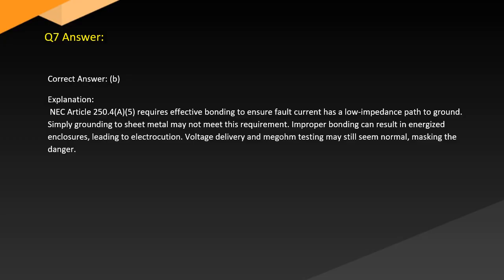Answer. Correct answer: B. Explanation: NEC Article 250.4(A)(5) requires effective bonding to ensure fault current has a low impedance path to ground. Simply grounding to sheet metal may not meet this requirement. Improper bonding can result in energized enclosures leading to electrocution. Voltage delivery and megohm testing may still seem normal, masking the danger.